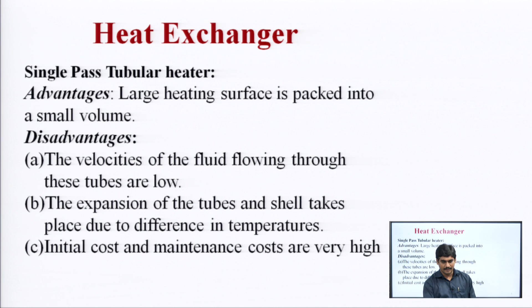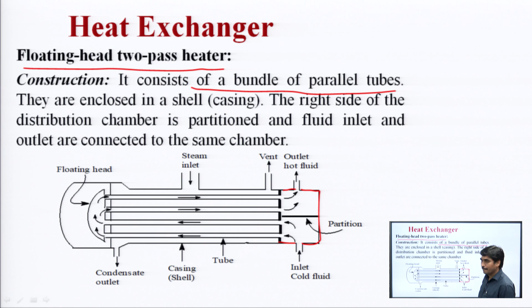Floating head, as the name suggests, means there is one portion which is floating, called the floating head. In the construction of this equipment, as you see in the diagram, it is also a bundle of parallel tubes as in the previous one, but there is a difference. In the previous instrument, there were 2 distribution chambers attached on both sides. In this case, only one distribution chamber is provided, with a partition in the middle, made in such a way that half of the tubes are on the bottom side and half of the tubes are on the upper side.